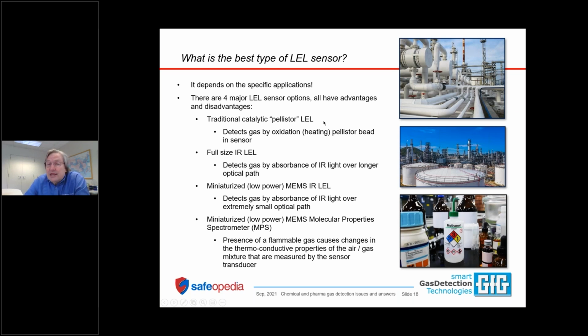So traditional catalytic LEL sensors, as we discussed, the alumina material in the active bead makes them particularly prone in pharmaceutical applications to being burned out by exposure to methanol. Methanol is not good for traditional catalytic LEL sensors. Also, traditional LEL sensors require the presence of oxygen in order to detect gas. Some substances like silicones can also poison them. We're not talking about fully cured materials that are made from silicone. What we're talking about is stuff like Armor All or RTV or silicone lubricants or other materials that release the silicone as they are curing.